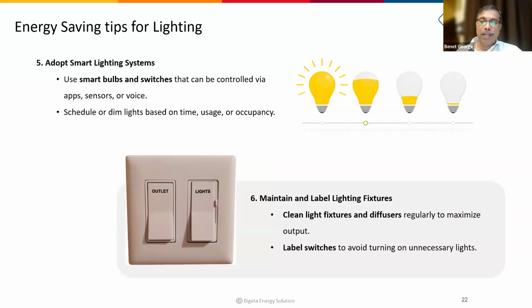Then always ensure clean light fixtures. If light fixtures are not maintained in a very clean condition, the lumen output will reduce. That is also called the lumen depreciation factor. So based on the type of fixtures, the illumination level will come down year by year. It is also important that we put names or labels on the switches, so that when people go out, they understand this is the light switch and this is something else, a power switch, so they can switch off.